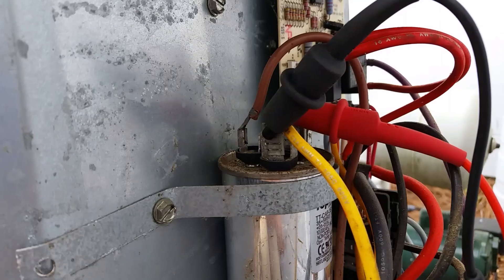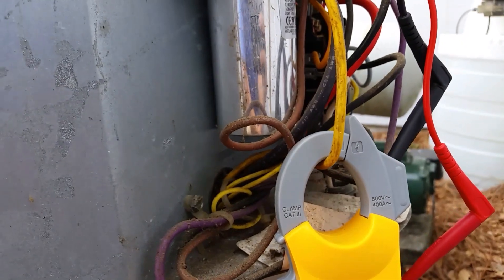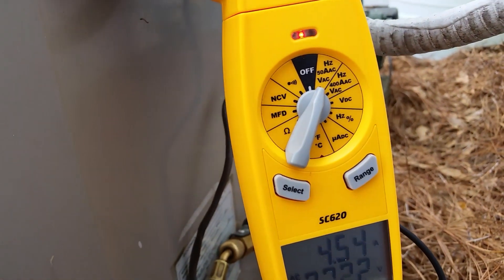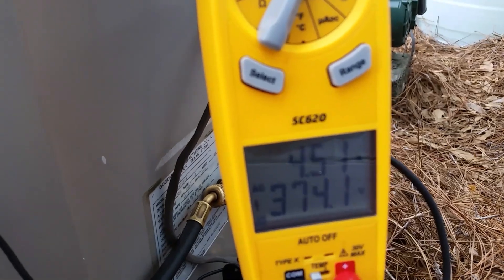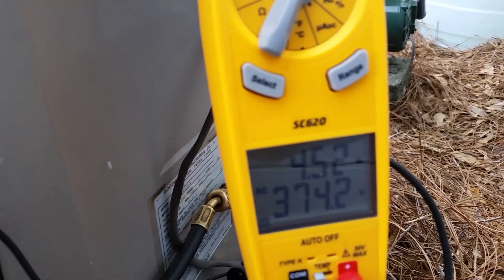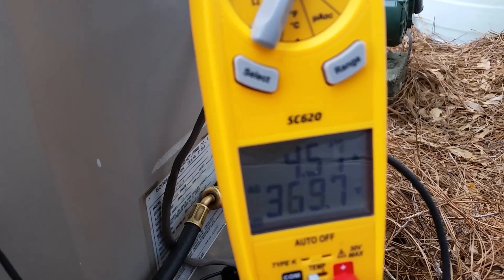We are hooked up at the reading leads right there. This yellow wire that our amp clamp is on is our start winding going to our run capacitor, using our Fieldpiece SC620. Hopefully you can see down there — 4.5, 4.56, somewhere in there. And we'll say about 370 for our voltage.